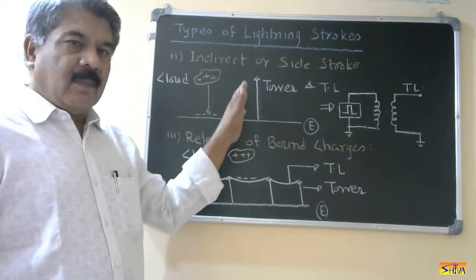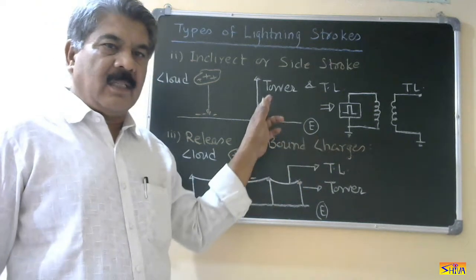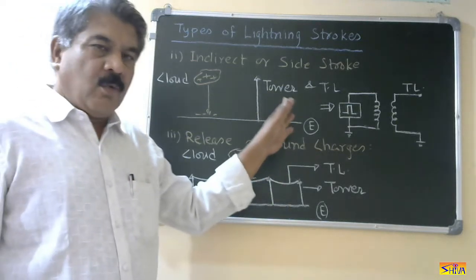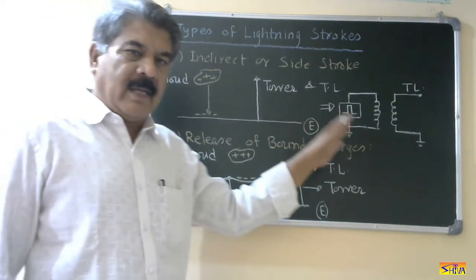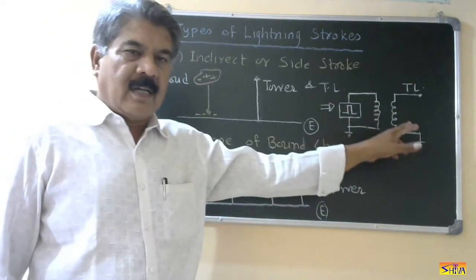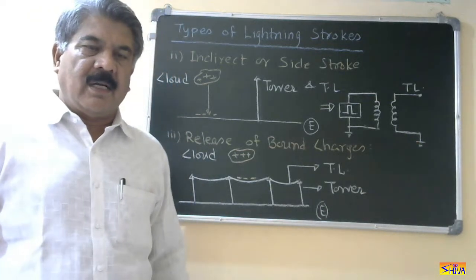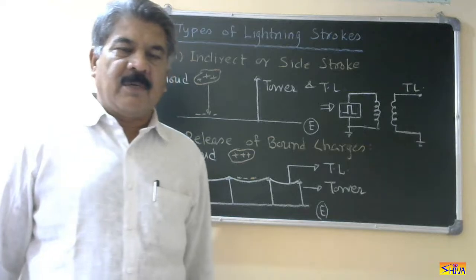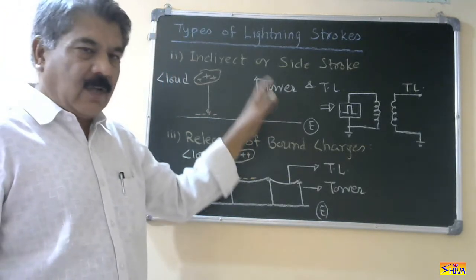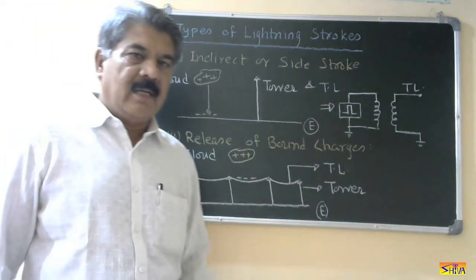When this type of discharge occurs near to the transmission line, a voltage wave of very high magnitude is induced in the transmission line because it acts as the secondary of a transformer. This voltage wave of very high magnitude — called a traveling wave — is established in the transmission line. I will explain in detail how these traveling waves damage the power system insulation afterwards. Since the discharge is not directly on the line or tower, it is called an indirect or side stroke.